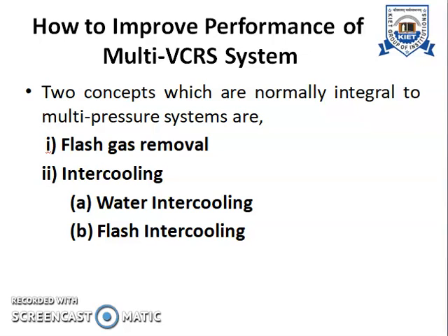Now intercooling is again of two types. First one we have water intercooling, where we employ cooling water for cooling of the refrigerant vapor coming from the low stage compressor or a low pressure compressor. And second is flash intercooling, where we use liquid refrigerant for cooling the vapors which are coming from the low pressure compressor. Okay.